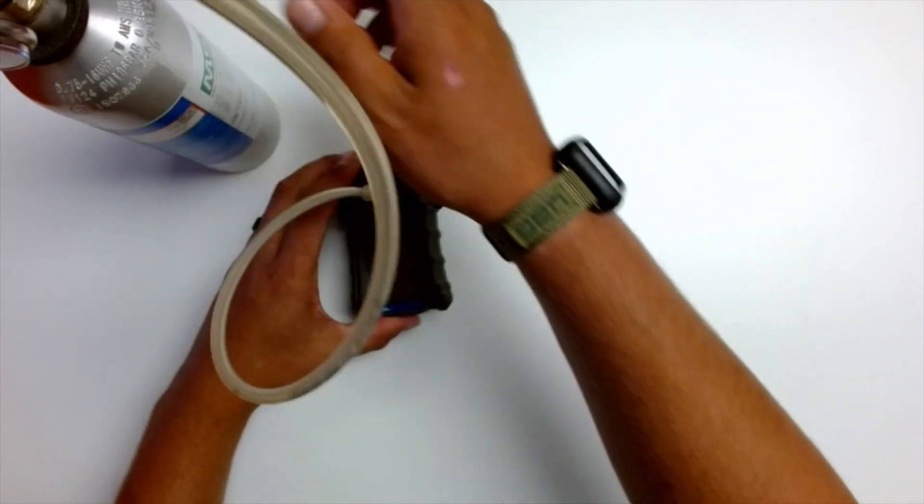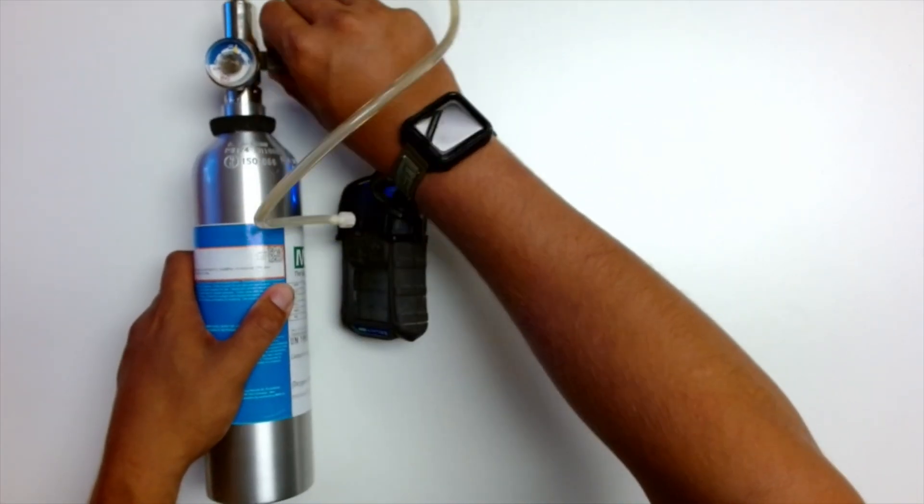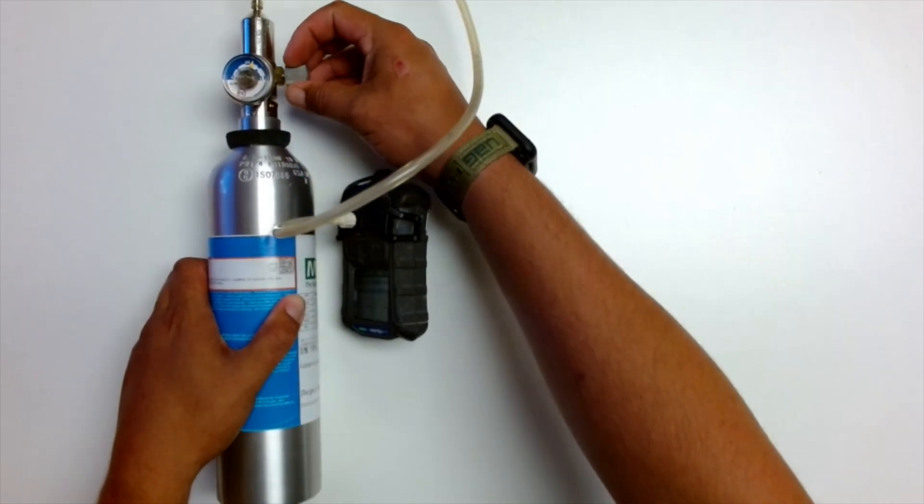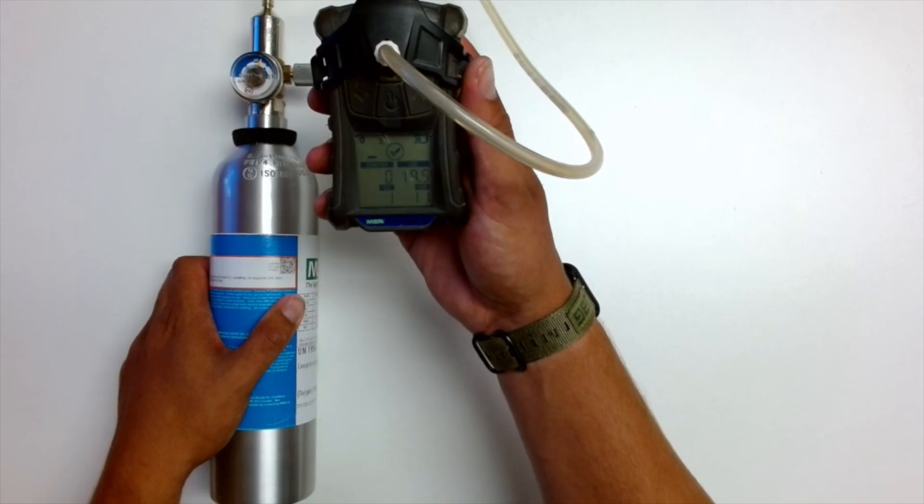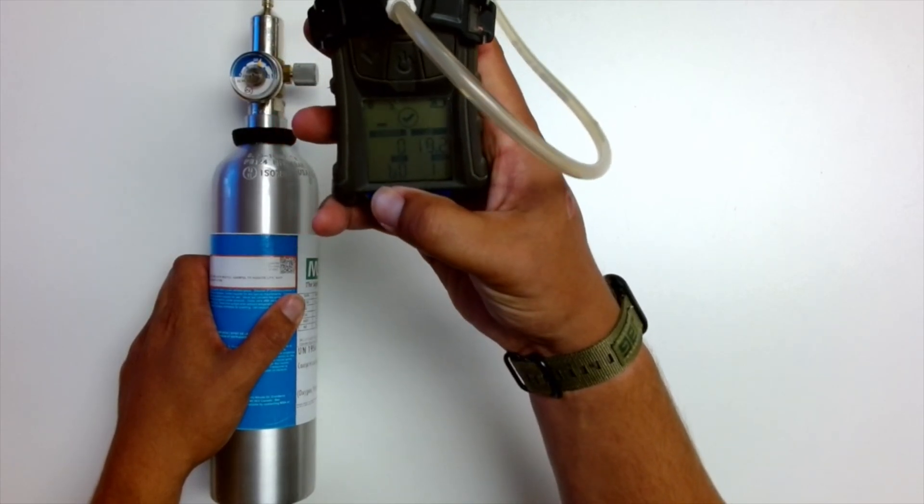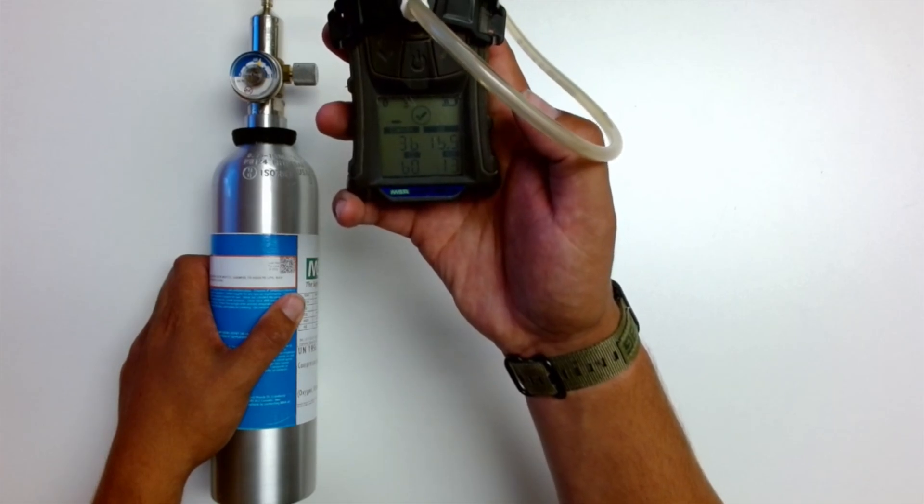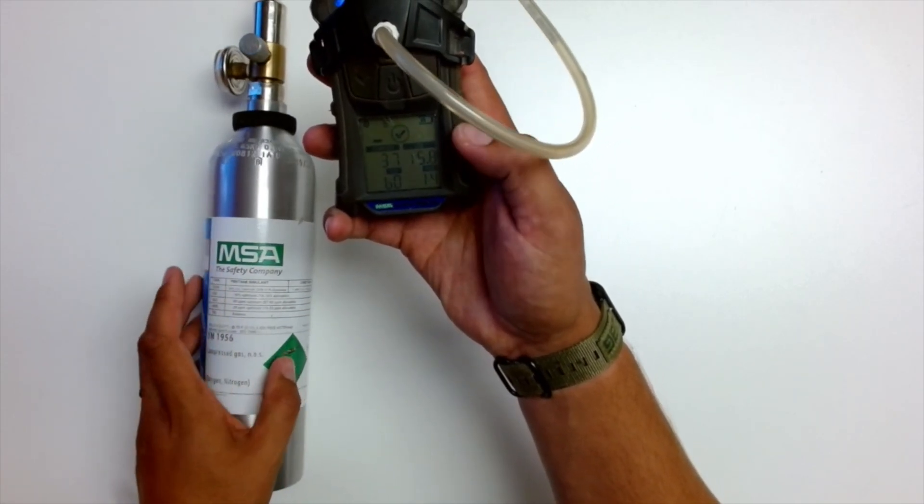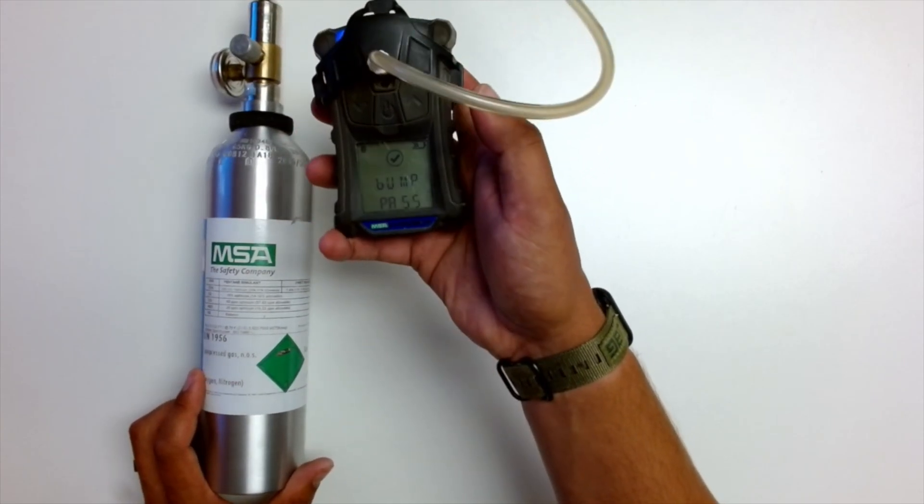The monitor here is flashing saying we're ready for gas. So I'm going to turn my calibration cylinder on, and then gas will be applied to the monitor. And you'll see the values will change throughout your bump test, basically showing how much concentration of the gas is hitting the sensors inside the monitor. We should soon get a pass.